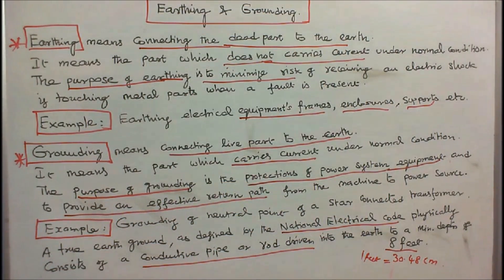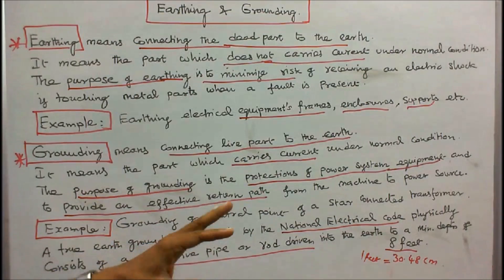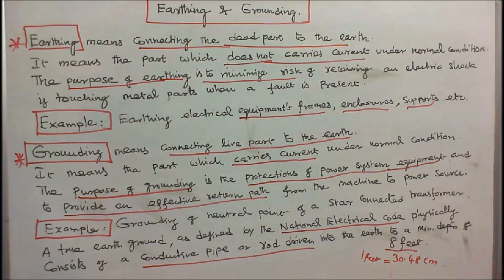Example: grounding of neutral point of a star connected transformer. A true earth ground as defined by the National Electric Code physically consists of a conductive pipe or rod driven into the earth to a minimum depth of 8 feet. One foot is equal to 30.48 cm.